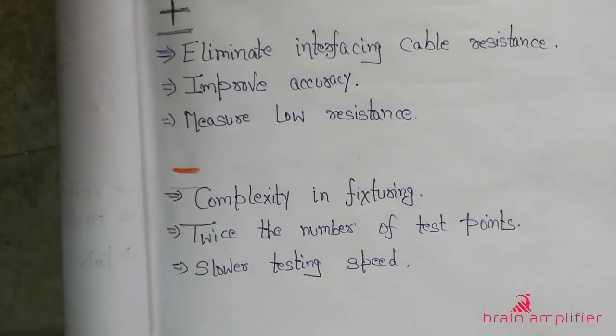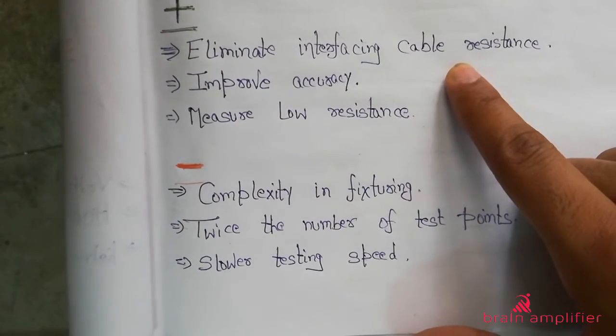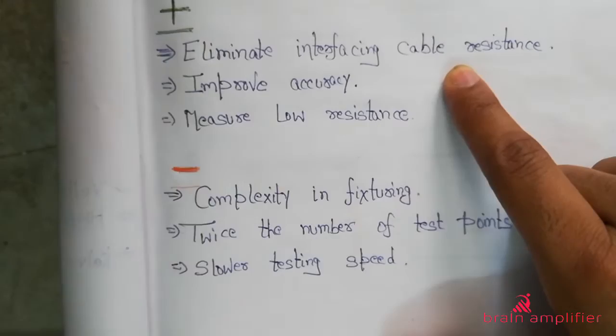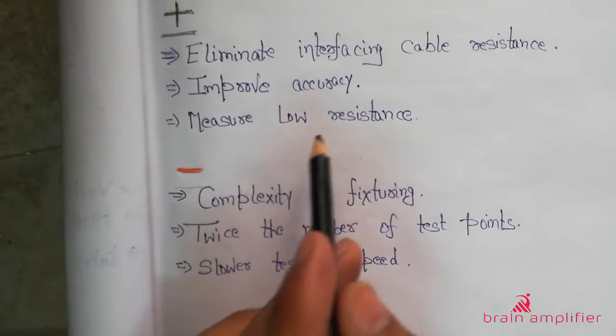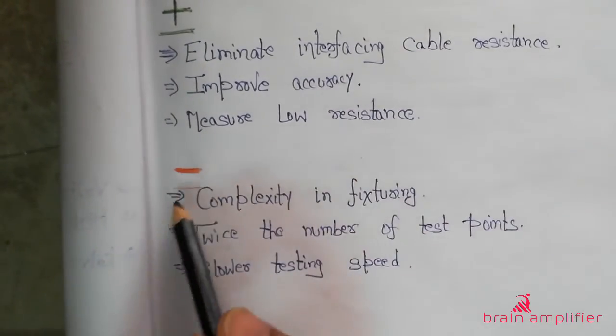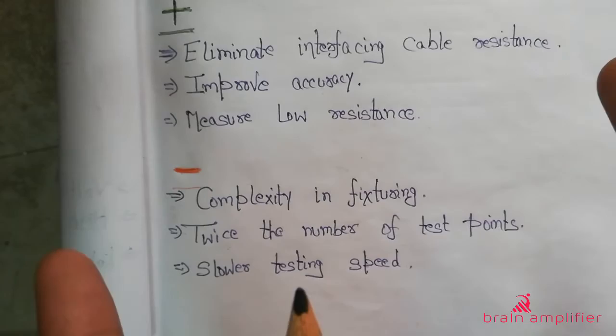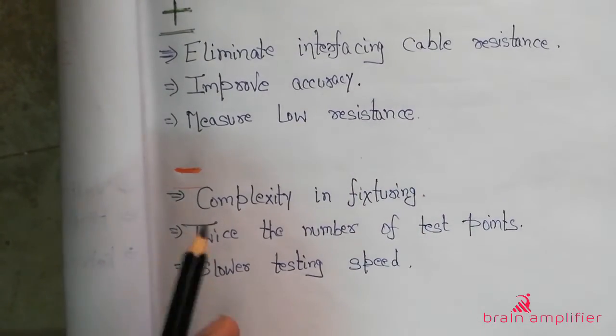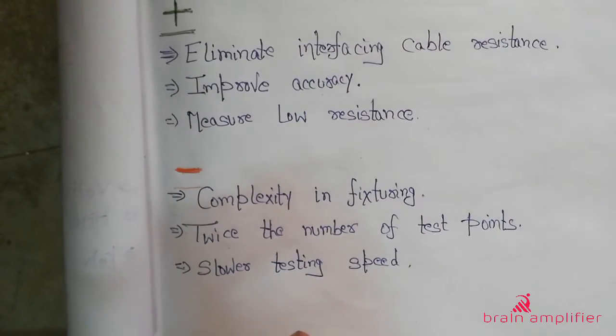There are some pros and cons to this method. The benefits: it eliminates interfacing cable resistance, improves accuracy by removing that resistance, and it can measure very low resistance values. The negative points: in the two-wire method you just put the multimeter leads on the resistance. But here you have twice the number of test points — you have to put four clamps across the resistance — so it takes more time, testing speed is slower, and there are added complexities.